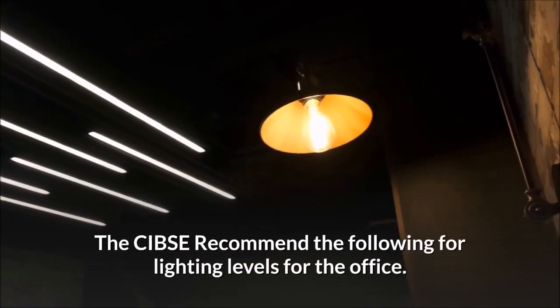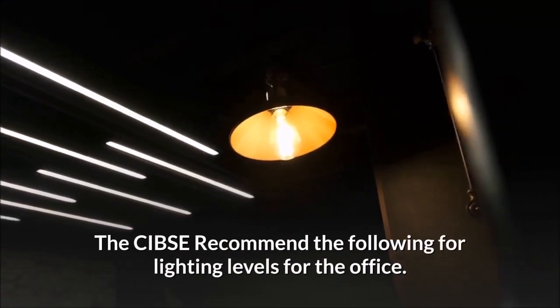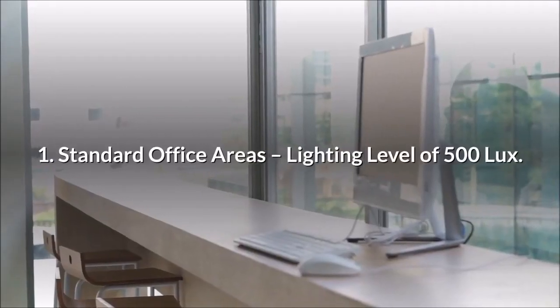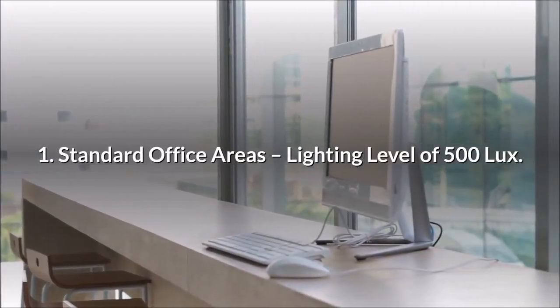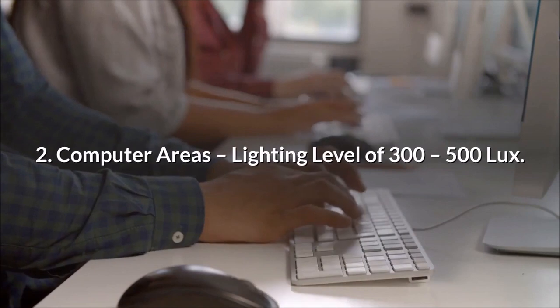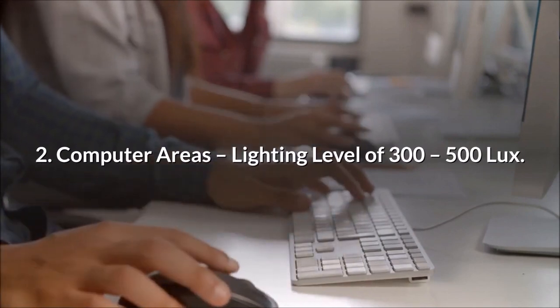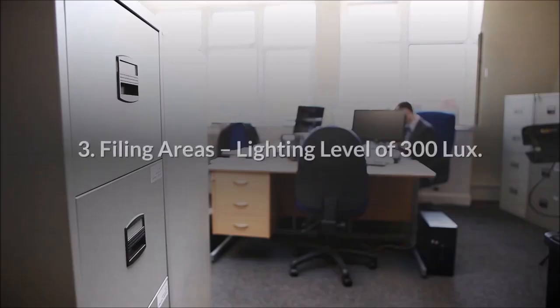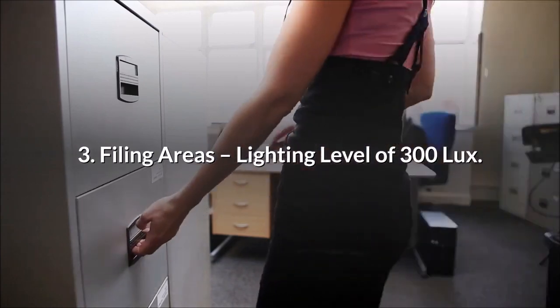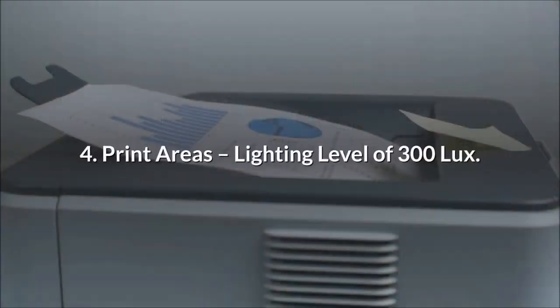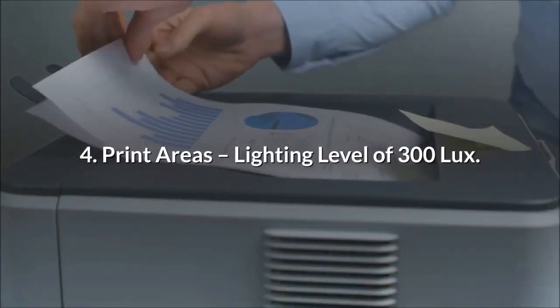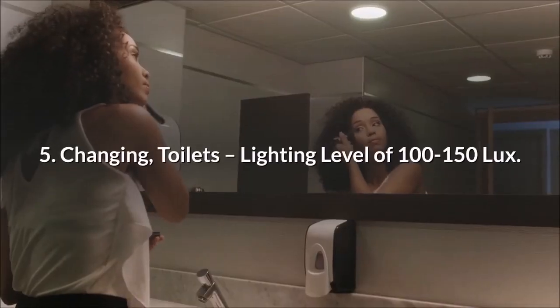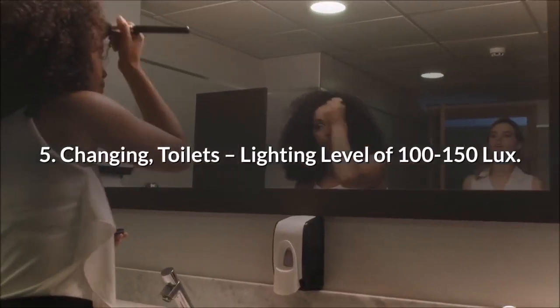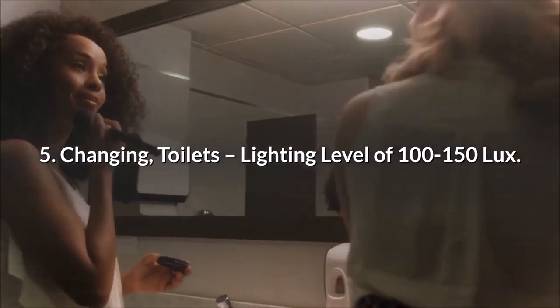The CIBSE recommend the following for lighting levels for the office. 1. Standard office areas, lighting level of 500 lux. 2. Computer areas, lighting level of 300 to 500 lux. 3. Filing areas, lighting level of 300 lux. 4. Print areas, lighting level of 300 lux. 5. Changing, toilets, lighting level of 100 to 150 lux.